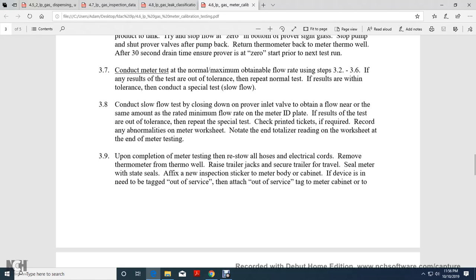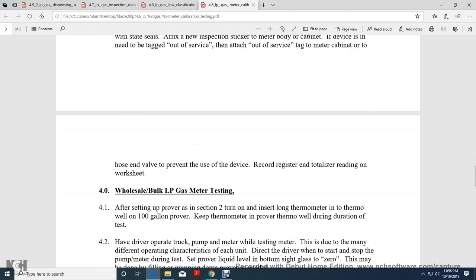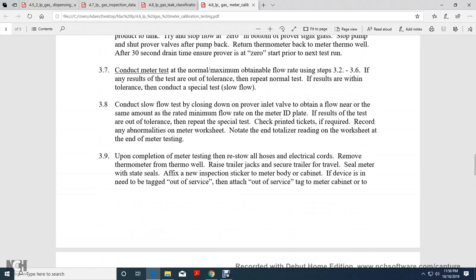Check printed tickets if required. Record any abnormalities of the meter on the worksheet. Note the end of the totalizer reading on the worksheet at the end of the meter testing. Upon completion of the meter testing, re-stow all hoses and electrical cords. Remove the thermometer from the thermo well, raise the trailer jacks, and secure the trailer for travel. Seal the meter with the seals.